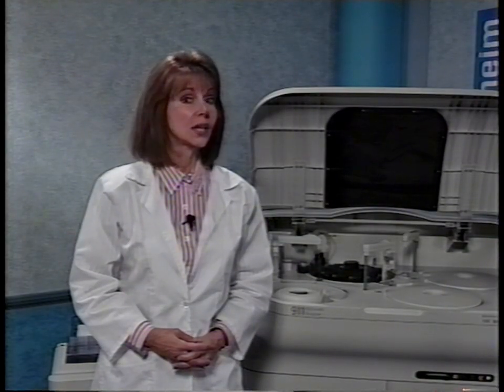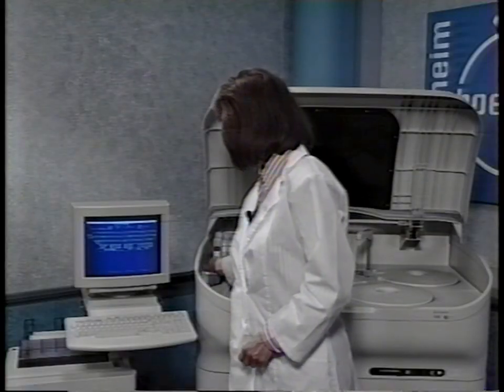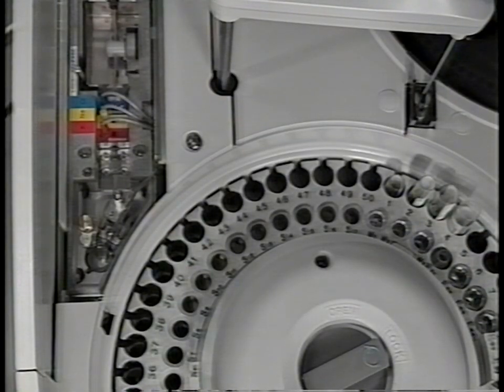Well, that covers the processing and measurement of photometric tests, and we're ready to move on to the ion selective electrode, or ISE system. We'll see how it measures concentrations of sodium, potassium, and chloride ions in patient samples and controls. The ISE sampling system uses the same sample probe used for the photometric tests. The pipetted samples are dispensed and diluted in the dilution vessel here.